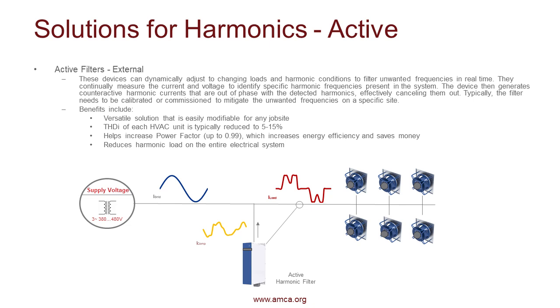And then with this, you're actually effectively canceling out those harmonics. So you're actually looking at what harmonics are on the site, on your grid, and you're removing them or canceling them out. With this, you do have to calibrate the filter. You have to look at each site and maybe figure out what is better for one site versus another site. But it's an optimal solution. It's a flexible solution because maybe your site is changing over time as you add more nonlinear loads to that site.